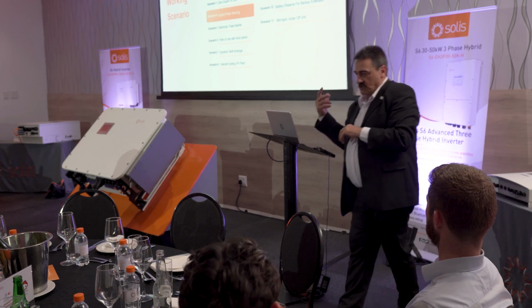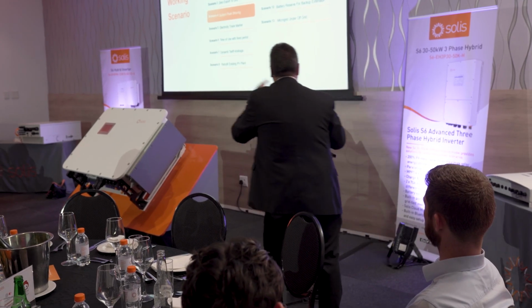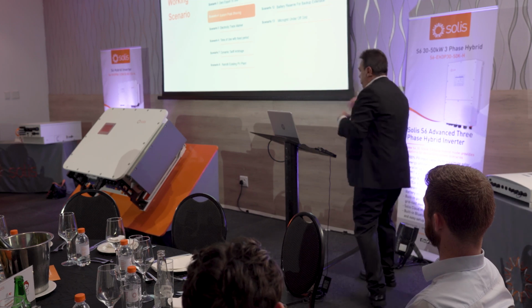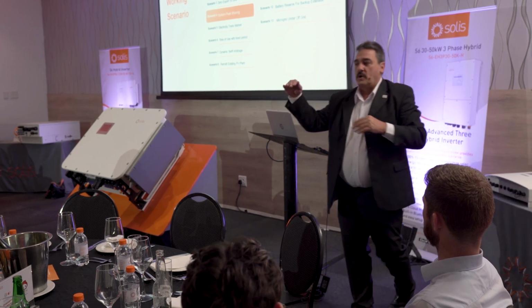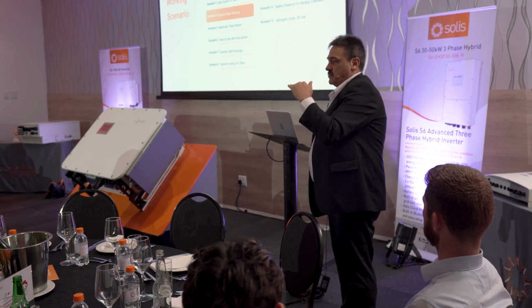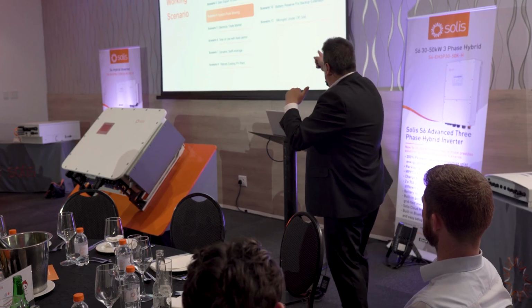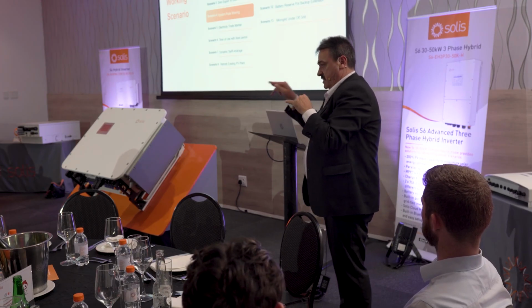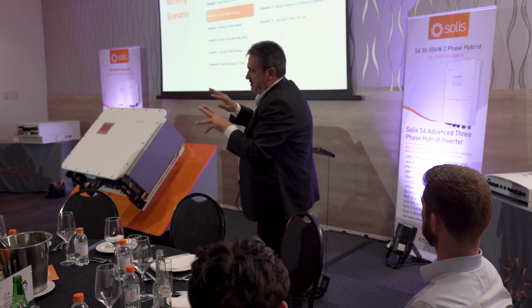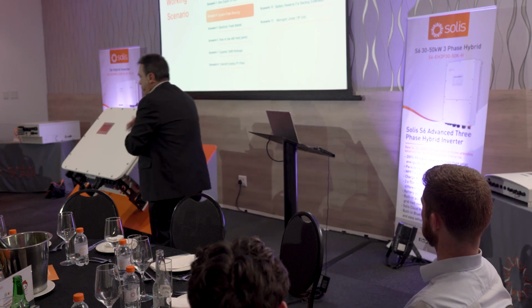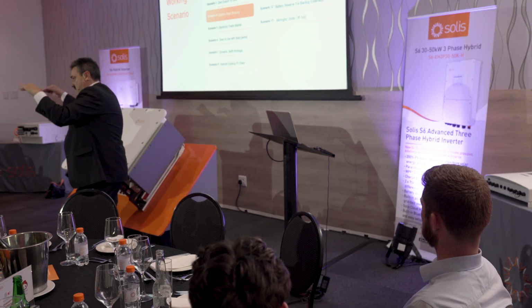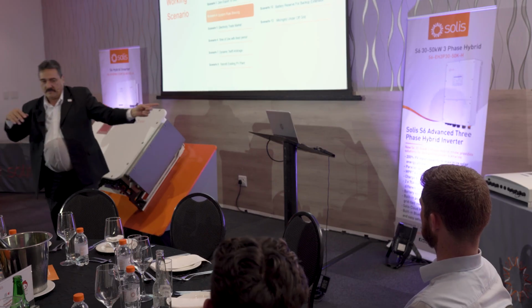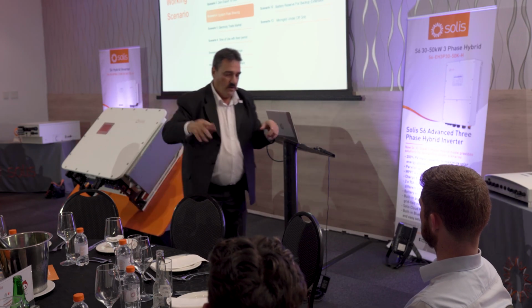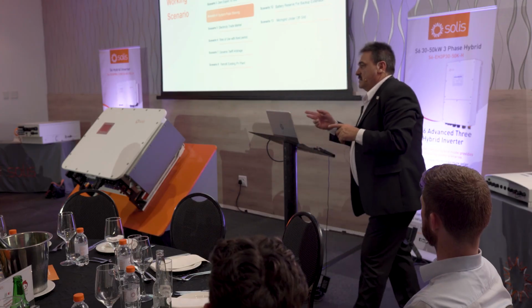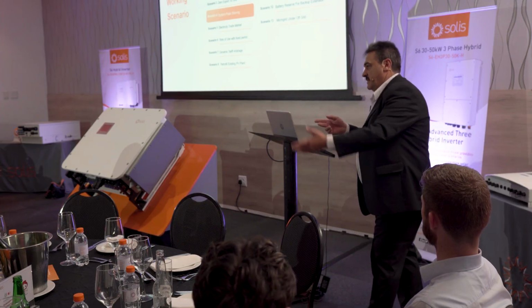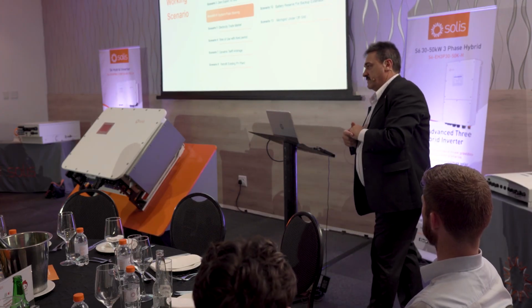So the inverter's got a system commonly referred to as peak shaving. You set a setting in the inverter to say we do not want to exceed this amount of power coming in from the grid. The meter on that side will check it, put a guard there. Then as soon as that power creeps up to that level, the management system kicks in and says, hang on, we can't go over that, and it will start discharging from the battery to keep that load within spec.